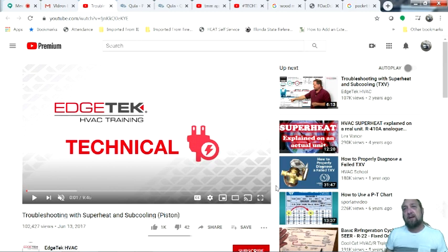You could say overcharging, like there's too much. Actually, superheat is talking about how warm the evaporator or suction line is. Excessive superheat means there's not enough freon in the suction line. You could be low on charge or have a restriction.